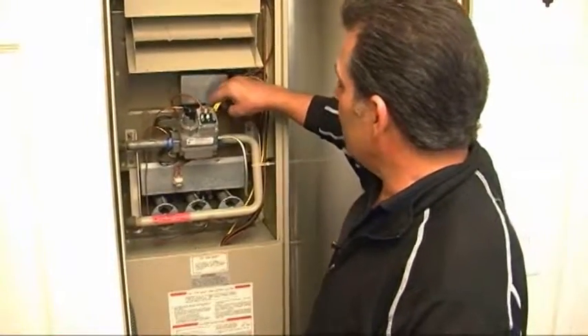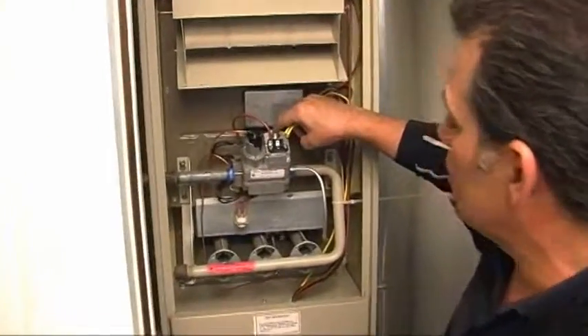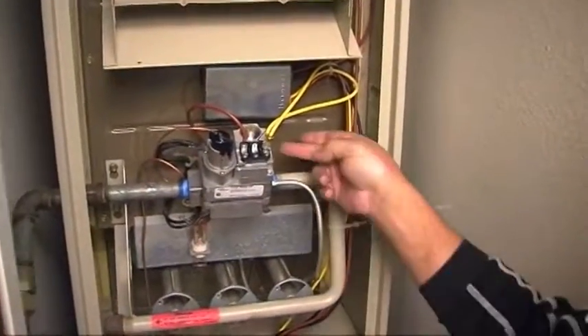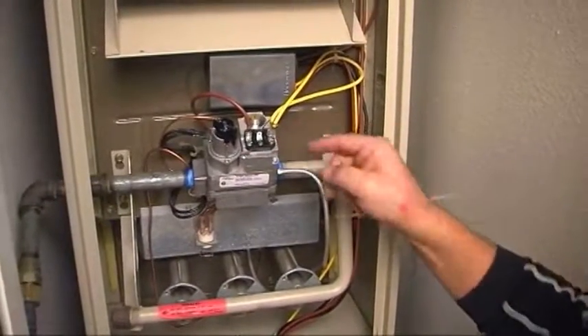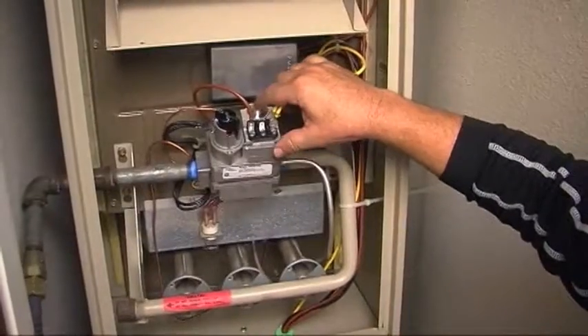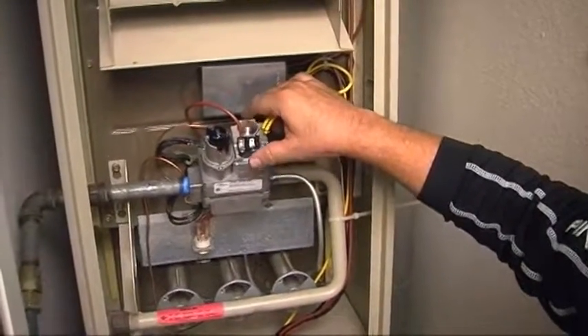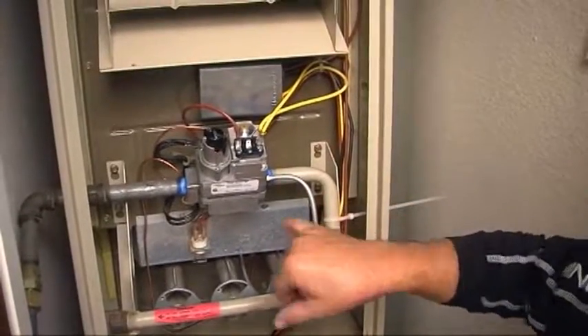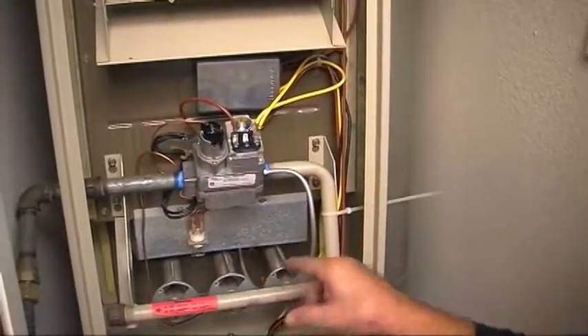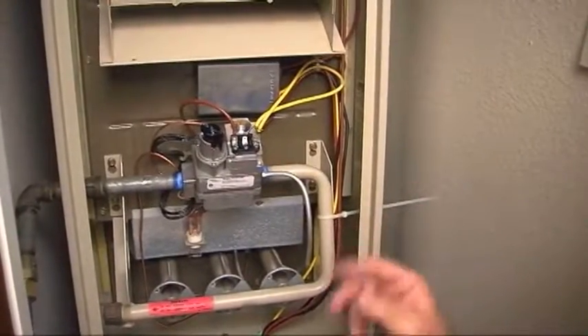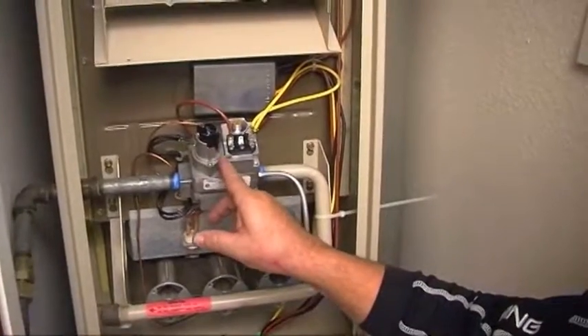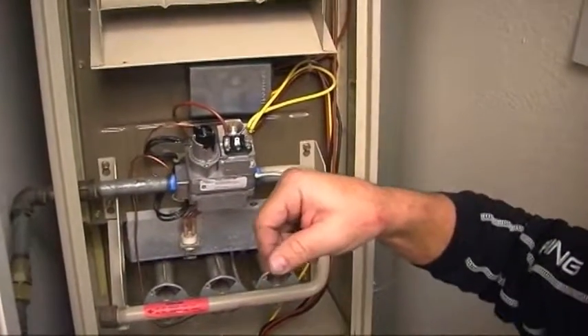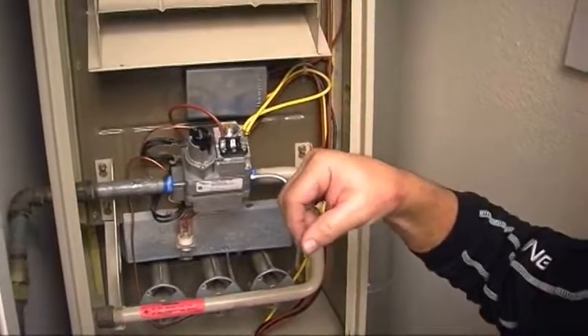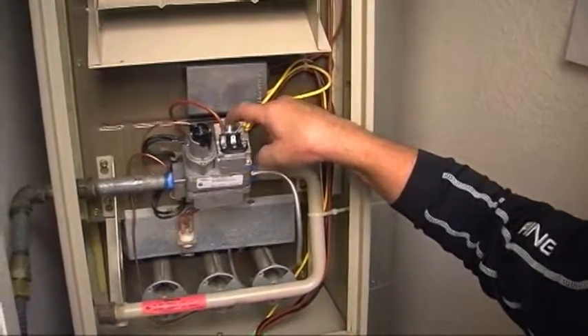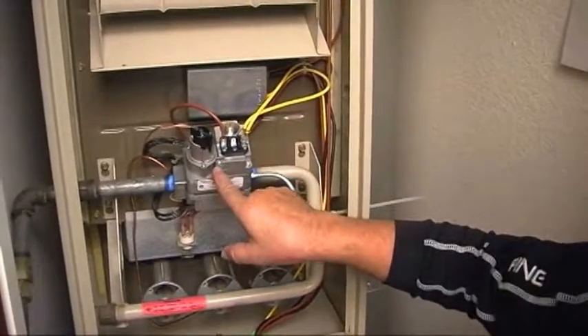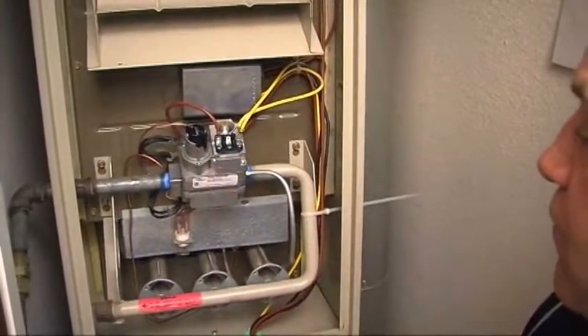While we're here, I wanted to tell you that this screw right here, when you unscrew it, that's where you adjust the gas pressure, in order to do your manifold test port right here. When you're doing your combustion test, if you need to increase your CO2, you need to turn down on the spring in that area. This screw right here is your pilot adjustment. If your pilot isn't high enough and isn't strong enough onto the thermocouple, you would unscrew this, put your screwdriver in, and turn counterclockwise for the pilot. Clockwise for more pressure because we have a spring on the regulator of the gas valve, and counterclockwise for more pilot fuel going through the pilot.